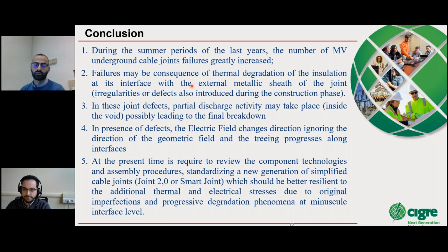We can arrive at the general conclusion, which we can summarize in these five points. As we said, during the summer periods of recent years, the number of medium voltage underground cable joint failures greatly increased. These failures may be a consequence of thermal degradation of the insulating material, in particular at the interface with the external metallic shield of joints.